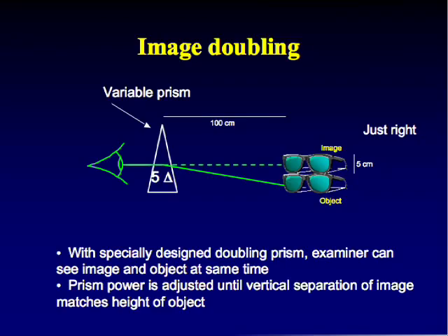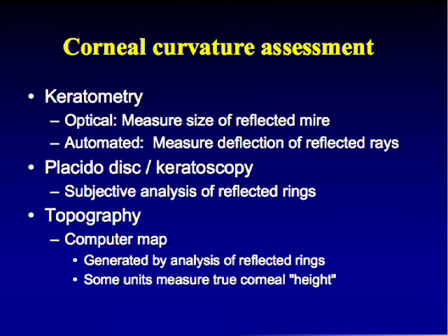Well, we don't go measuring glasses on children who are jumping on trampolines, but we do have to measure things on the surface of the eye under high magnification. And so this ability to use optical doubling or image doubling is invaluable. It also takes advantage, you'll see later, of your vernier acuity because you're trying to make a line join to a line.